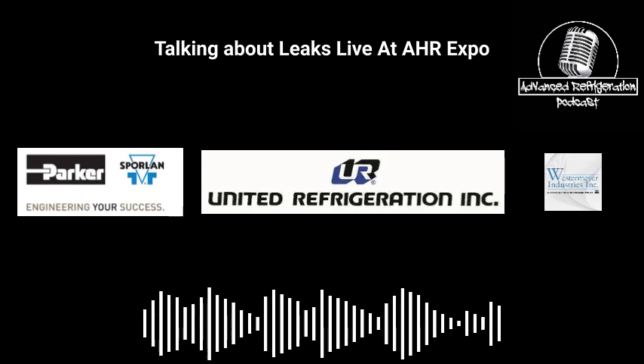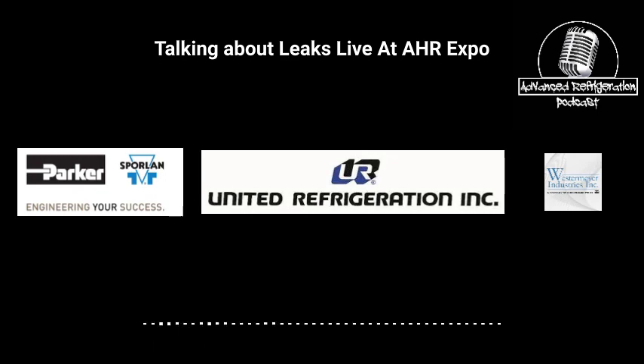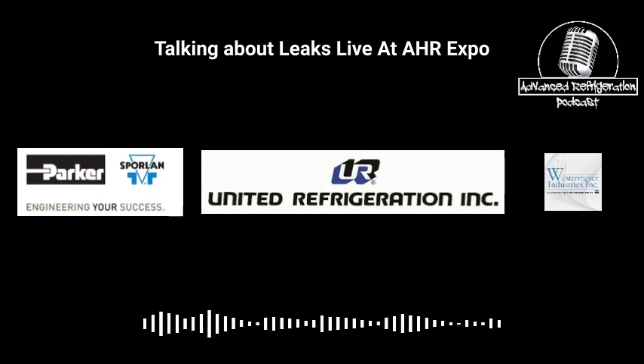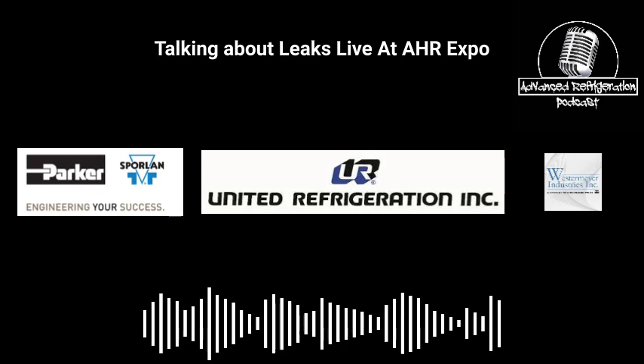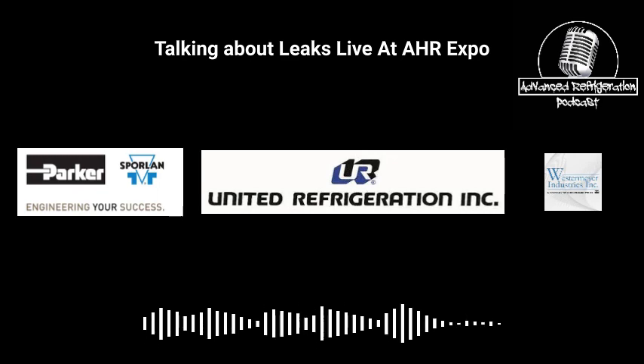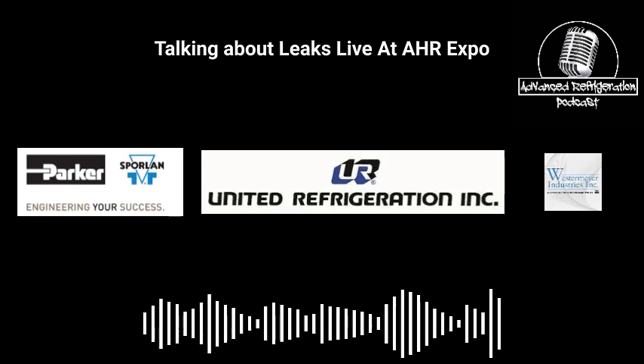Same thing with what you were talking about, leak mitigation, right? One of the things that could potentially be causing leaks is the wrong feet on compressors. Something as simple as that, you know what I mean? I've seen racks where they came with metal feet, and 99% of the time a scroll comes with rubber feet on the bottom. You've got 3 lines on there: discharge, vapor injection, and suction. And then all of a sudden, you start cracking suction lines because that compressor's moving. If you watch it, it doesn't look like it's moving that far, but it's moving far enough that you'll see that whole thing shake, and it's able to actually crack that line.